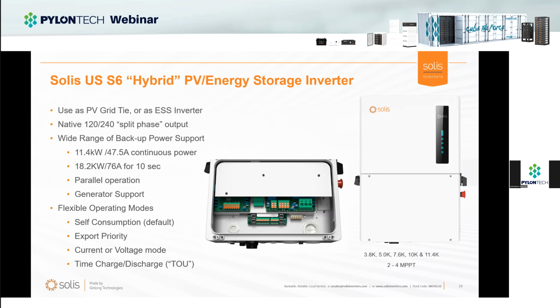We're getting 47.5 amps continuous out of a single inverter for one or two stacks of Pylontech. If you put two inverters in, you can get a couple of stacks and reach 95 amps of continuous power, with a 152 amp surge. It's an amazing capability now for these inverters to handle larger startups of big air conditioning units. For something like a 5-ton unit you might still need a soft start, but these inverters are now much more capable of handling typical whole home loads.